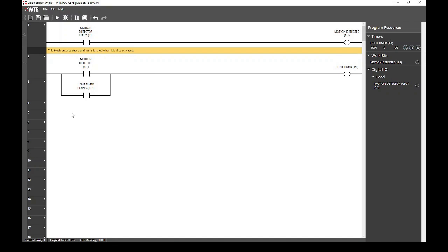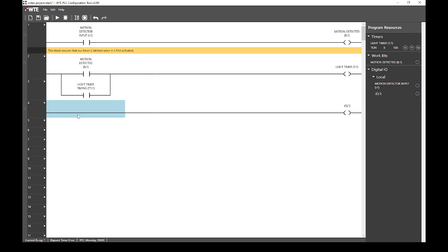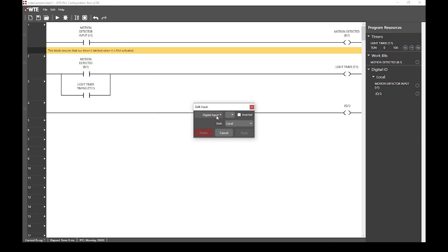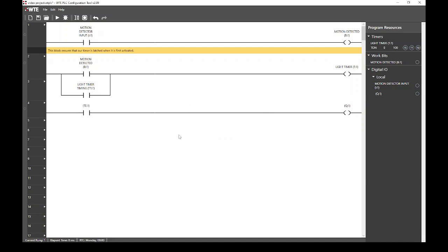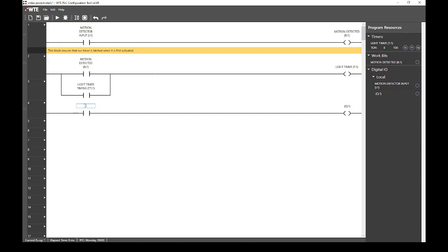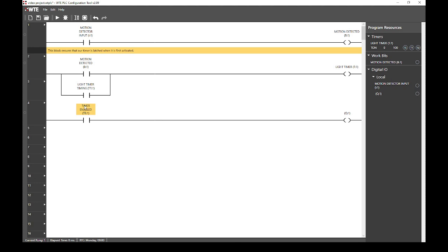Now that timer 1 is correctly set up, we want to attach it to digital output 1 so that we can use it to control our lights. We start by selecting rung 4, switching the rung type to main. Next, we select the first rung input position and we set the input to be a timer enable flag for timer 1. This flag is set whenever the timer 1 output is enabled. We will give it a descriptive name, such as timer enabled. Next, because this is already set to output 1, we will give this a descriptive name, light 1.